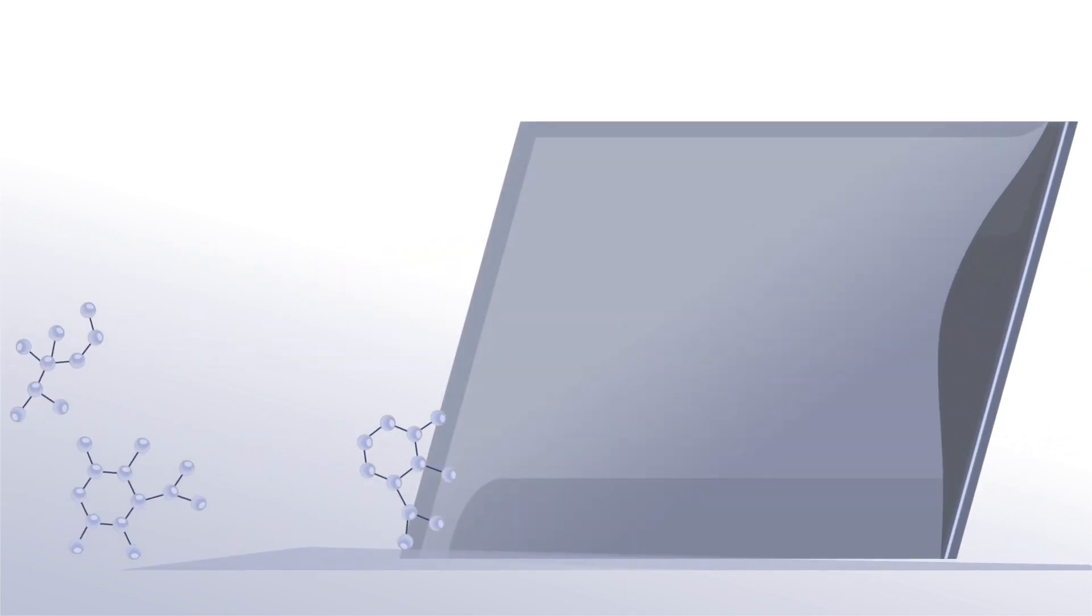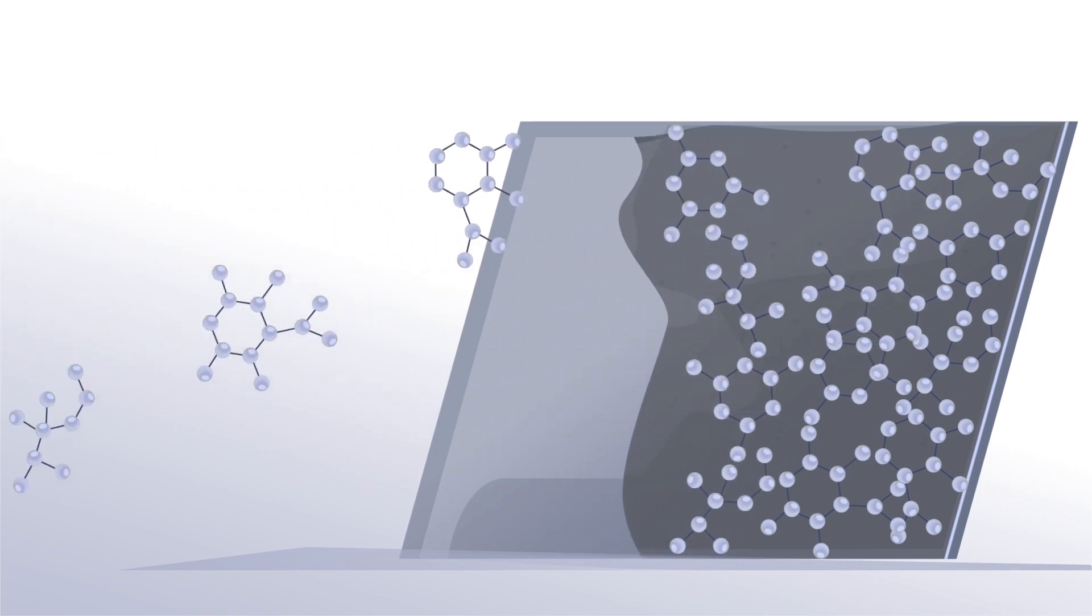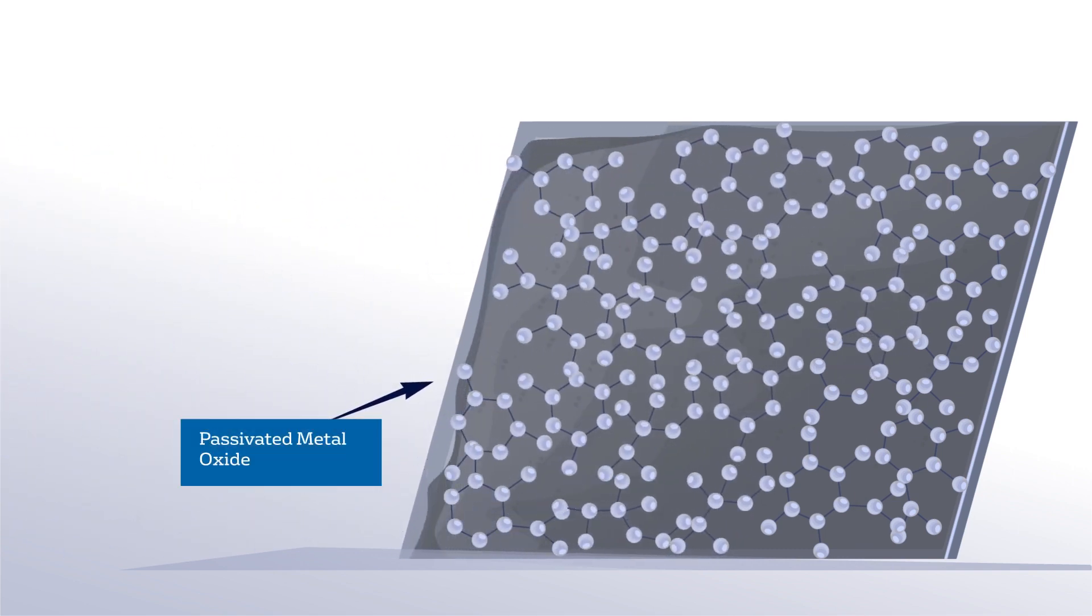When Ecofilm is introduced to the system, it begins templating the mild steel surfaces for film formation. This, in turn, begins to promote the formation of a passivated metal oxide layer on the surface.